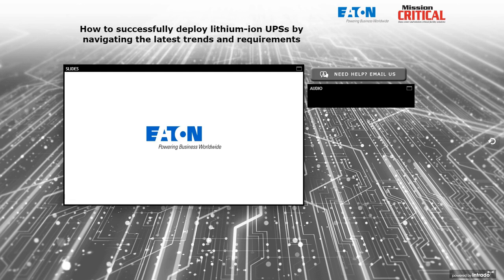Q: From a UPS point of view, what is the main difference between VRLA and lithium batteries? From a UPS operator's point of view, the biggest difference for customers is not necessarily the size and weight reduction — though nice — but the double expected service life. Whereas we tell clients to budget for complete battery replacement at the five-to-six-year mark with traditional batteries, our typical lithium-ion batteries carry a 10-year warranty on performance, and battery vendors expect a full 15 years of service life, which means the battery might actually last as long as the UPS itself.